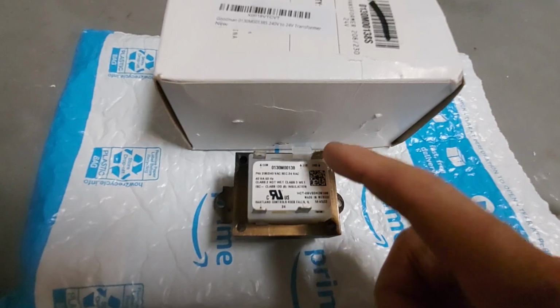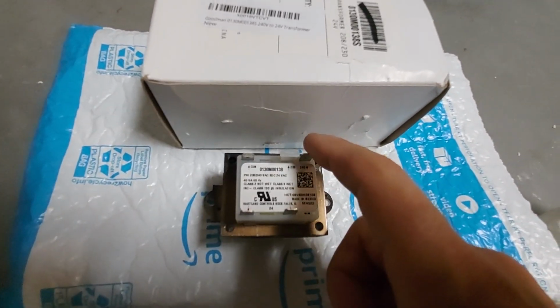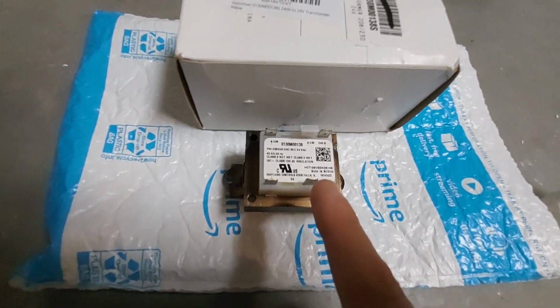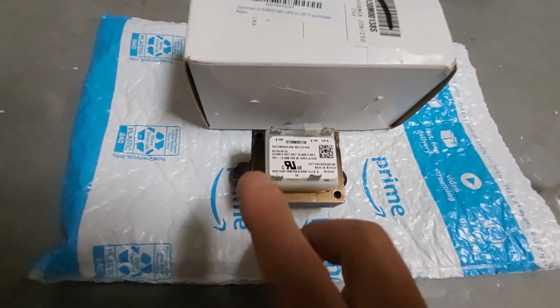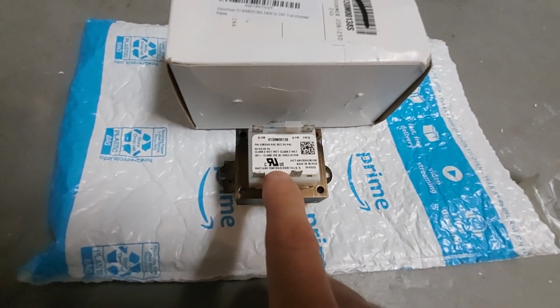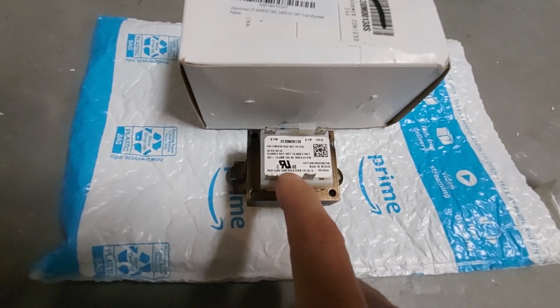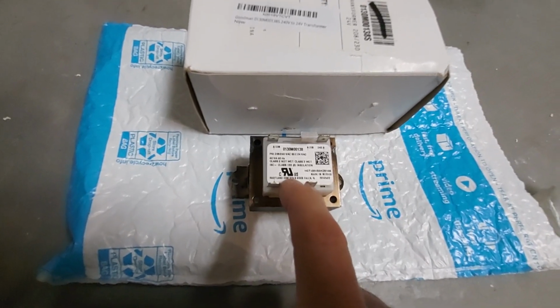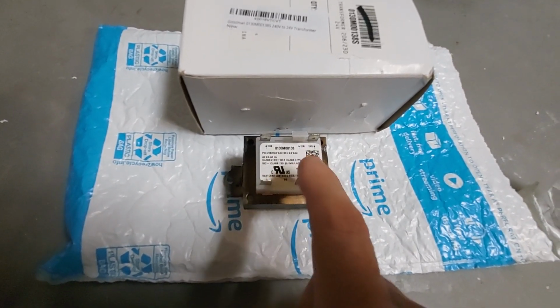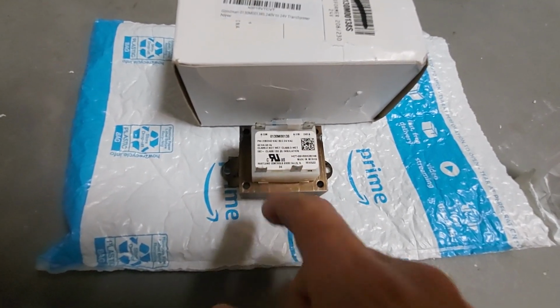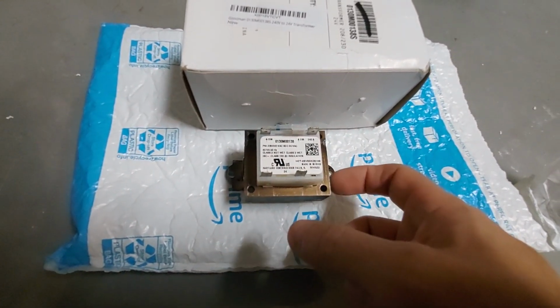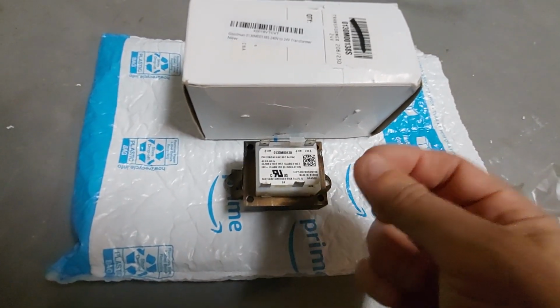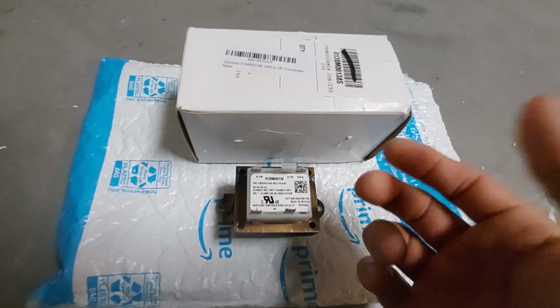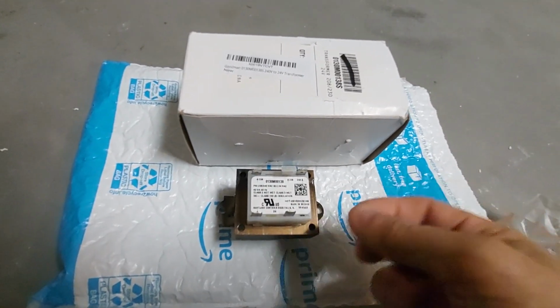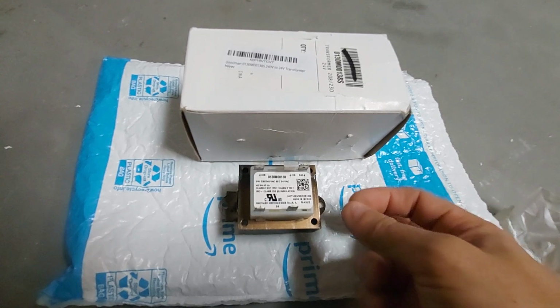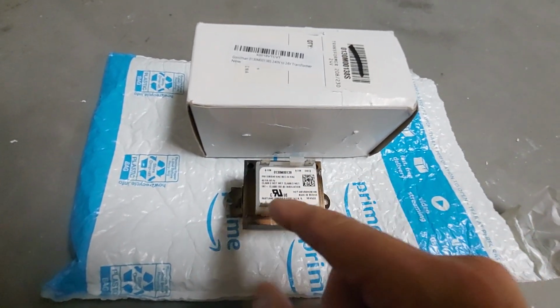Connect the high voltage, 230 or 240, to here, then take your meter and connect it to here. It's supposed to be 24, but you might see 28 - okay, it's a little higher. 29 is the most you want to go. If it's more than 29 output, forget it, you better return it, because it's probably cheap, or maybe when they were winding the coil, the varnish coating came off and bridged together.